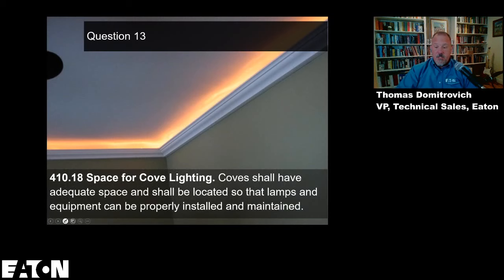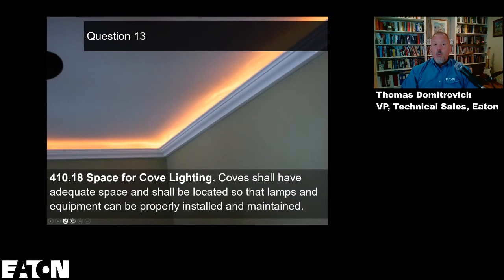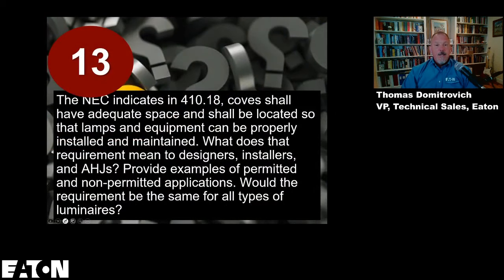These are a couple of the images that I saw. I don't know the intricate details around these designs because I didn't get on a ladder and climb up in there and take a look at it. But I know that some inspectors I've been with have pointed these types of images out, this one and this one in particular, and said they either would or wouldn't have permitted that because you don't have access to those without either removing the molding or some other method to get access to those components. But we're going to have to be able to provide that access that is required based on 410.18.